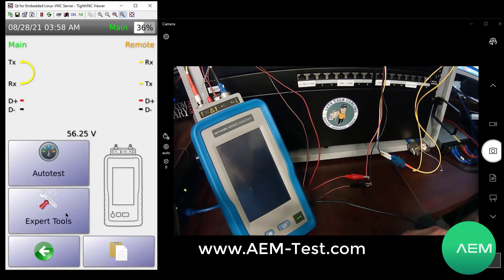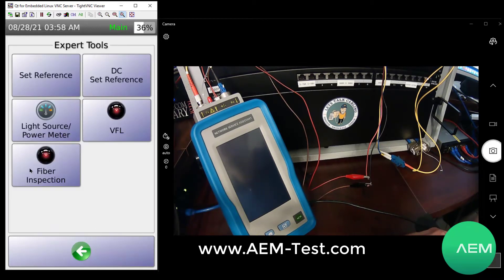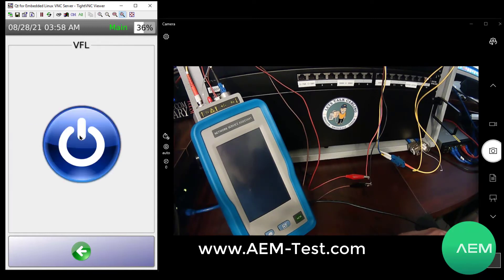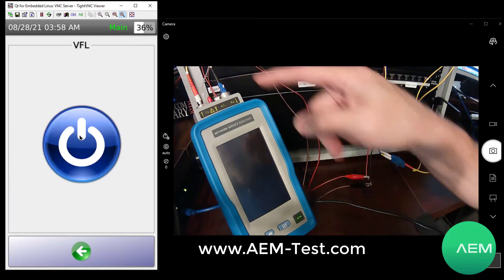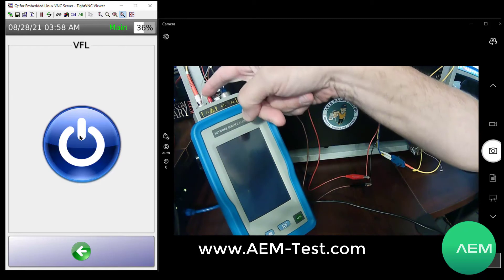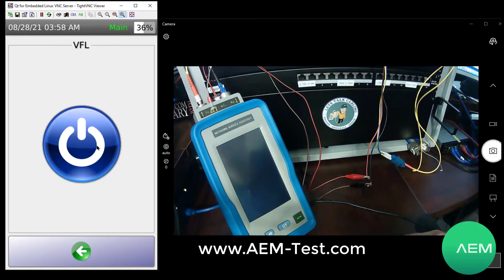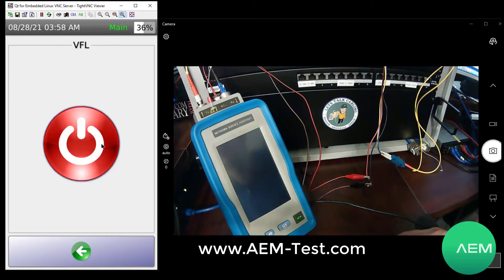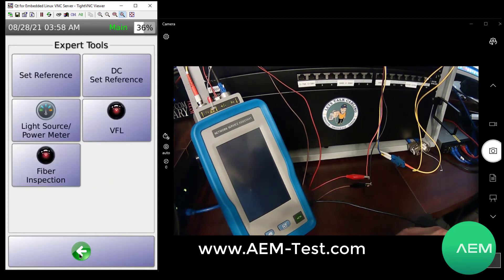Under expert tools, that's where you'll find the fiber inspection. You'll find the VFL built in here. If I hit the VFL and go ahead and turn it on, you can see the light start to blink — I've got a red protective cap on there, but it's pretty evident that it's blinking. That'll help you find a break typically at one end or the other in your distribution panel.